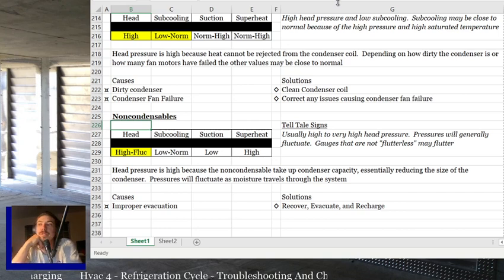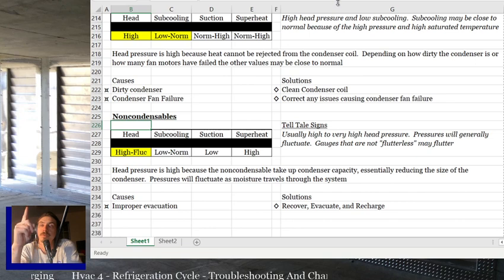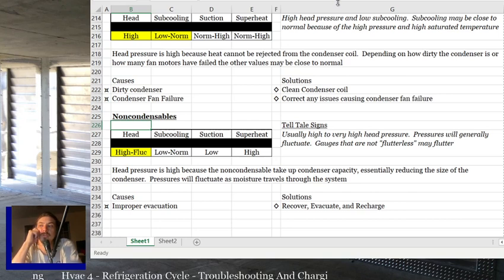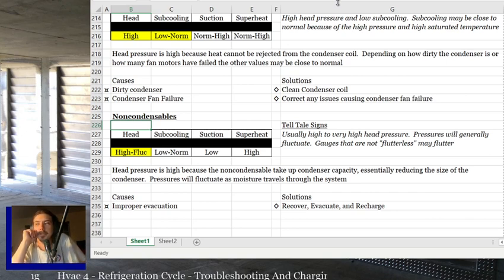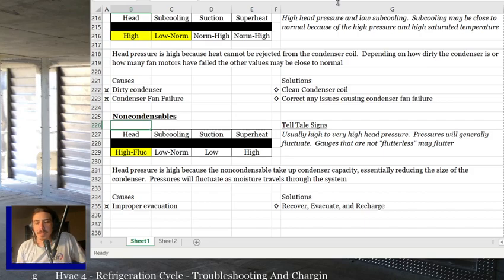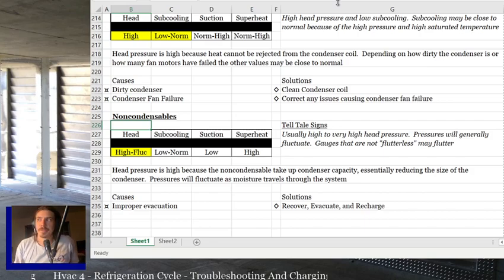There's something else. If you pump a system down and get it to the same temperature as outdoor ambient, the pressure that lines up with your saturated temperature should be the same as outdoor ambient. So if that doesn't work, then something's wrong with the refrigerant. You've got to take it out and put new refrigerant in after you've properly vacuumed and changed out your liquid line dryer. And hope there's not a ton of acid inside the compressor, basically.